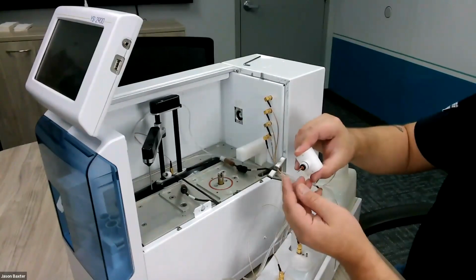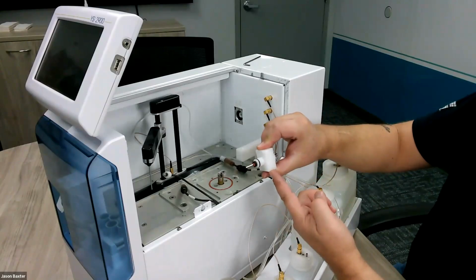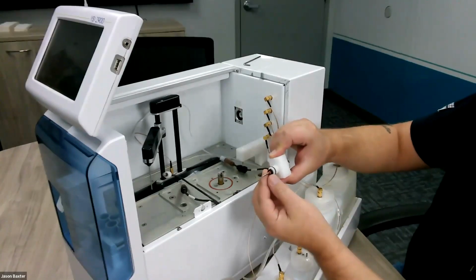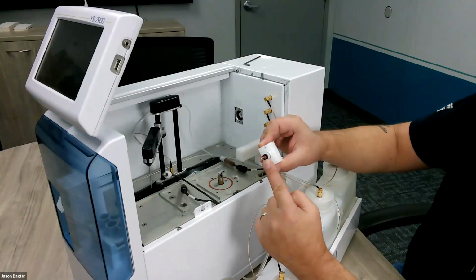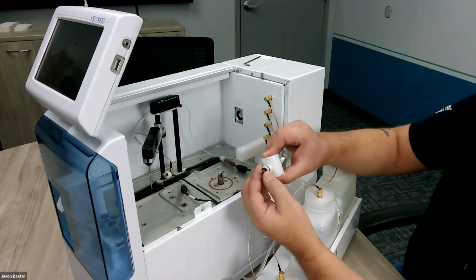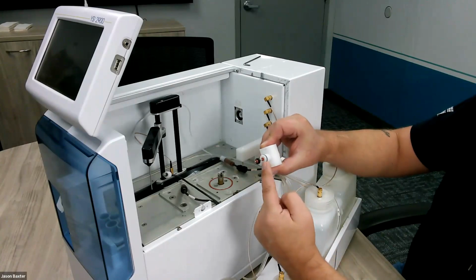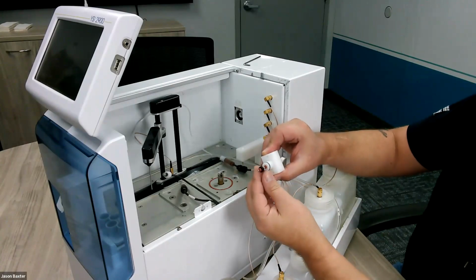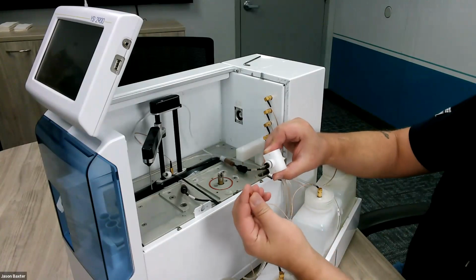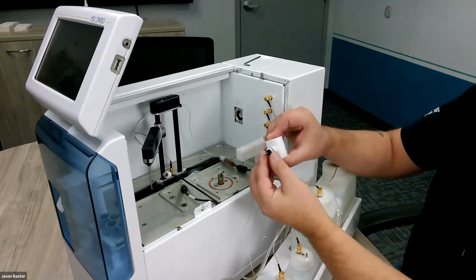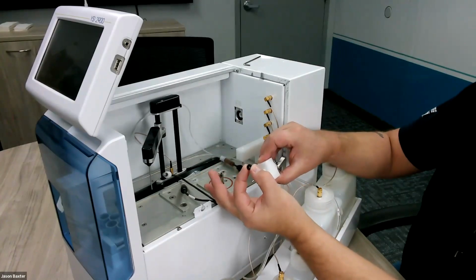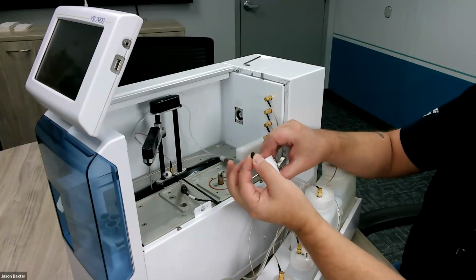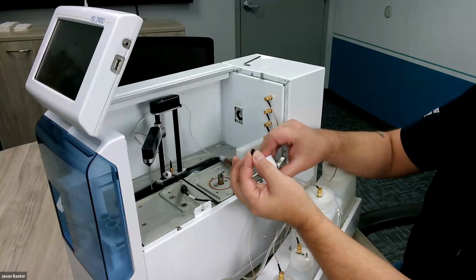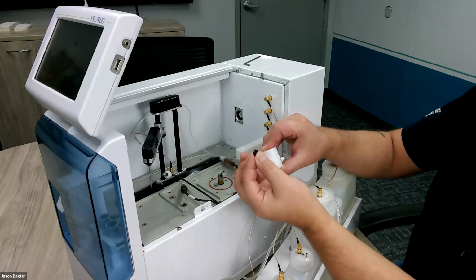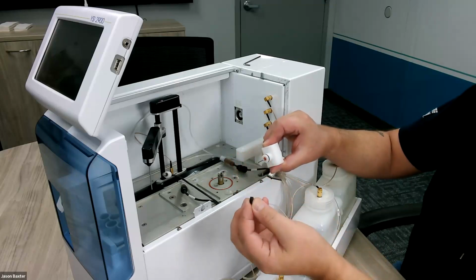Almost lastly, when you're taking your sipper pump body apart, you'll notice that there's a small orange O-ring at the front, and then there's a black spacer. If I pull these out somewhat, you'll notice there's a second orange O-ring behind. To remove this, simply take off the one orange O-ring and discard. One very important aspect is this black spacer. This black spacer is not included in the PM kit, but it is very critical to the function of the device. So please set this aside somewhere where you can find it and not knock it down the sink or onto the floor or anything of that sort.